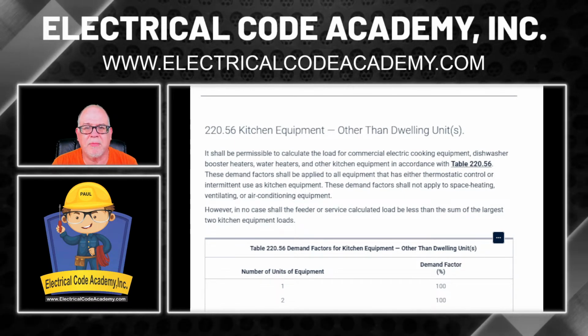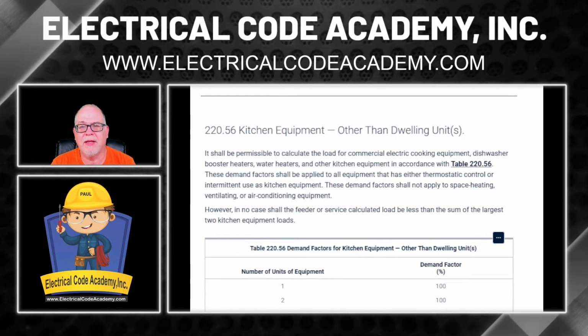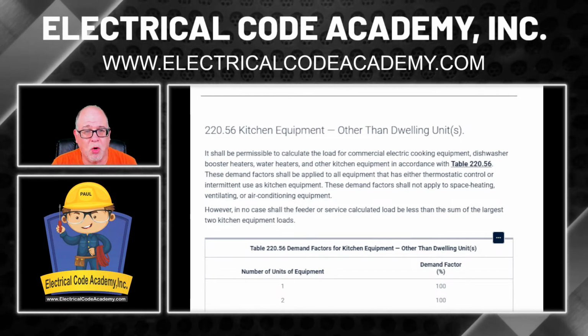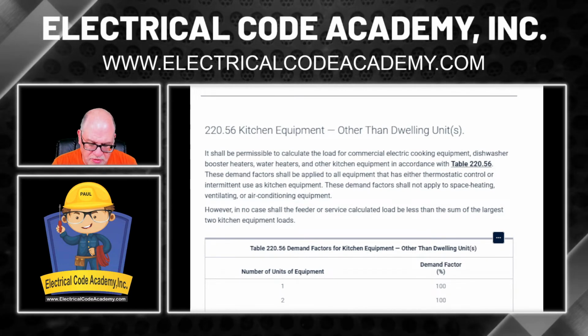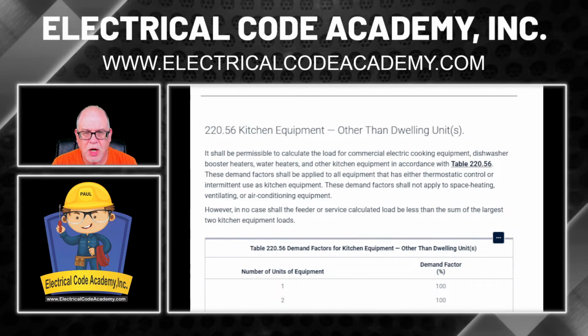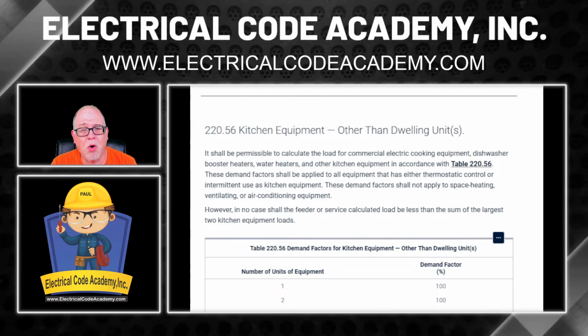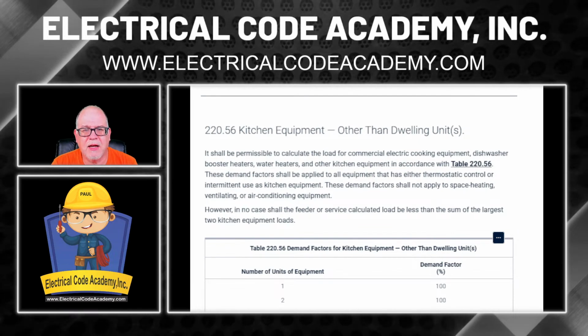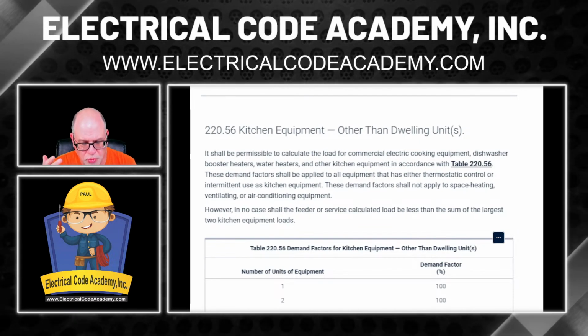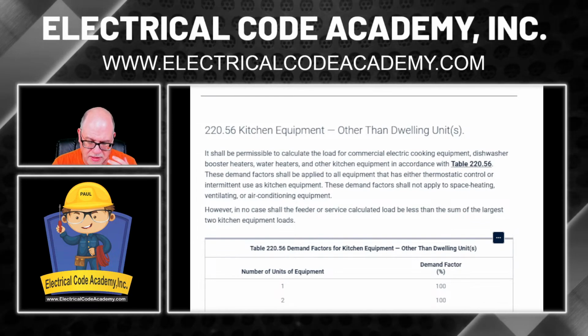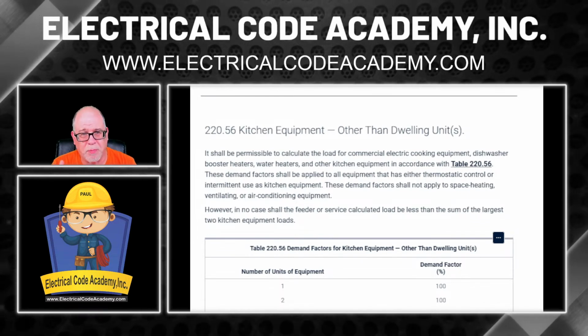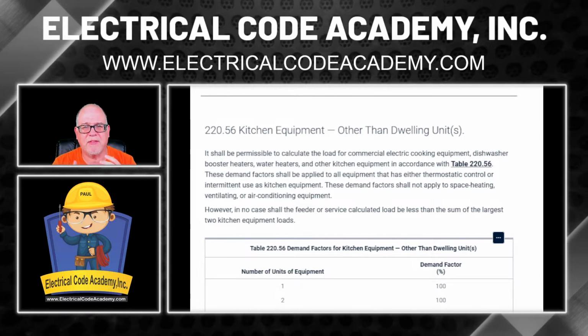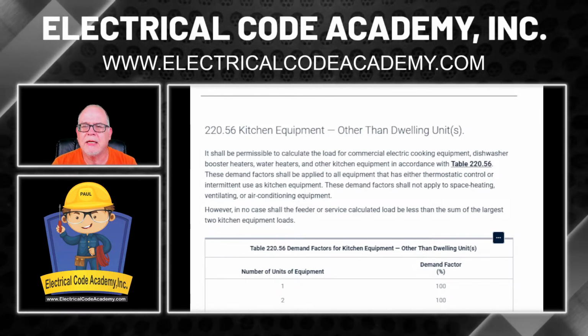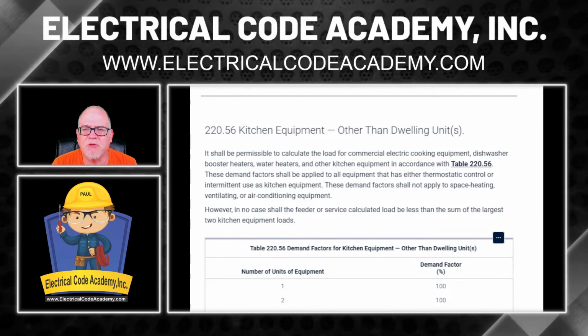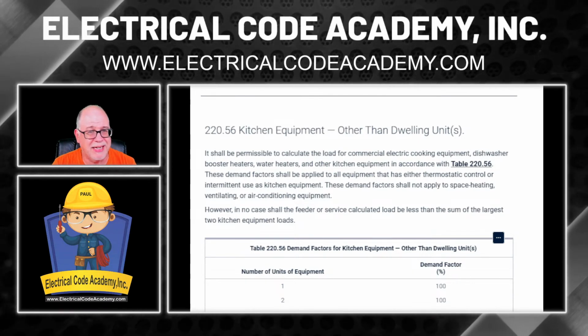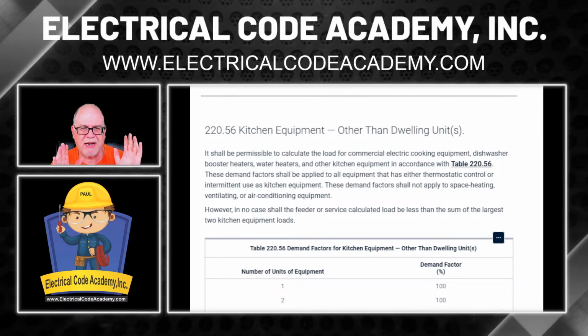It also says these demand factors shall be applied to all equipment that has either thermostatic control, and most of this stuff, the ovens, the grills, the deep fryers, and all that kind of stuff, is going to be thermostatically controlled. It says, or intermittent use in as kitchen equipment. Well, obviously, disposal's on when you need it. Water heater is going to come on when it's needed. Booster heater is going to come on when it's needed, but that's also probably thermostatically controlled. So we're good with all these pieces of equipment. It also says these demand factors shall not apply to space heating, ventilating, or air conditioning equipment. Yeah, because we got our own rules for that. So not going to have anything to do with that.